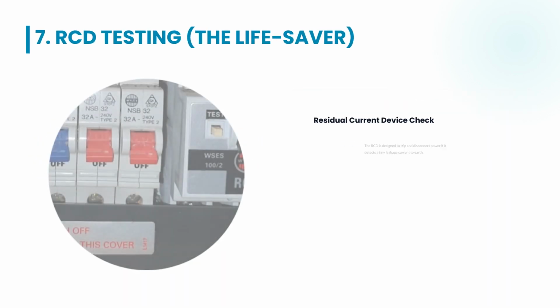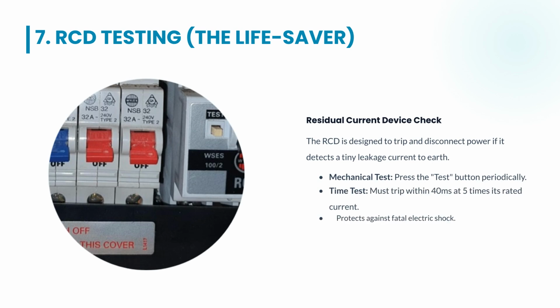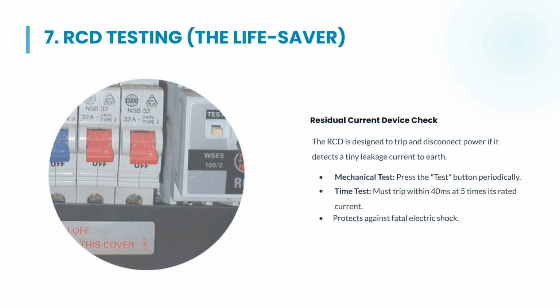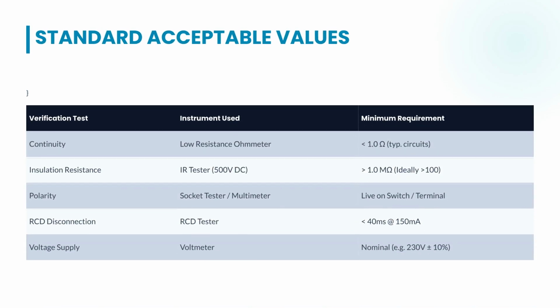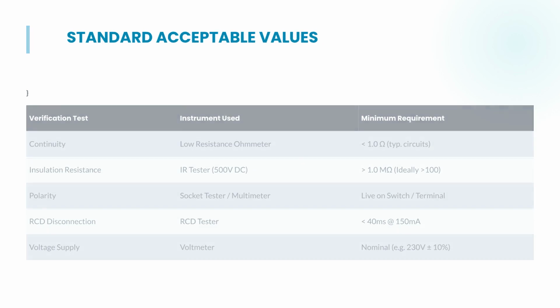The RCD test is a lifesaver, ensuring the residual current device trips and disconnects power when a small earth leakage current is detected. It involves both a mechanical test and a time test, ensuring tripping occurs within 40 milliseconds. This table summarizes standard acceptable values for various verification tests, including required instruments and minimum compliance requirements for continuity, insulation resistance, polarity, RCD disconnection, and voltage supply.